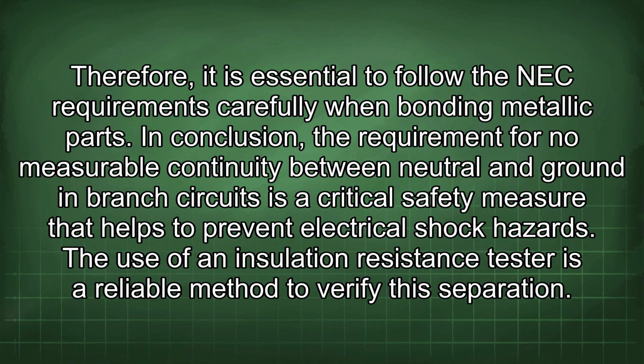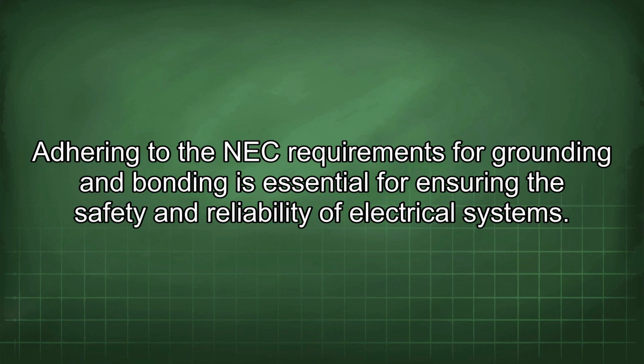In conclusion, the requirement for no measurable continuity between neutral and ground in branch circuits is a critical safety measure that helps to prevent electrical shock hazards. The use of an insulation resistance tester is a reliable method to verify this separation. Adhering to the NEC requirements for grounding and bonding is essential for ensuring the safety and reliability of electrical systems.